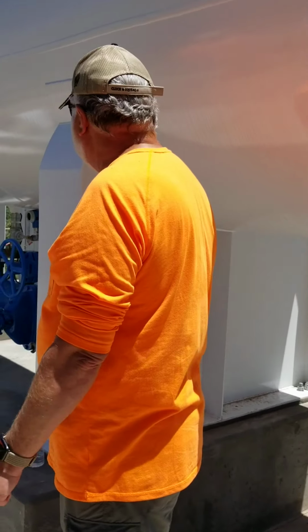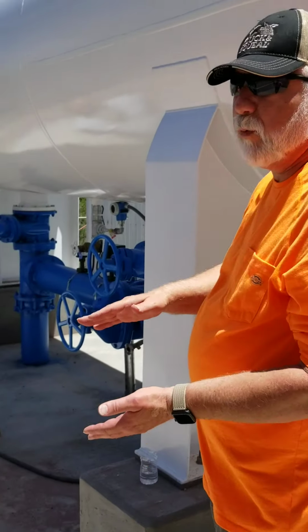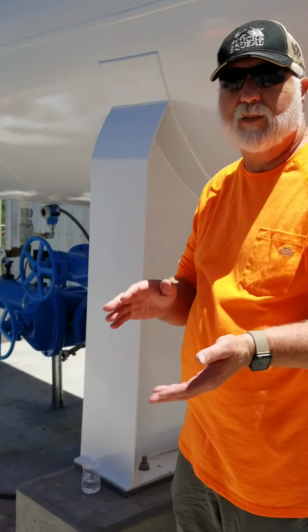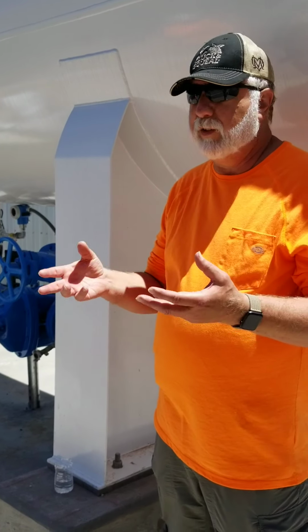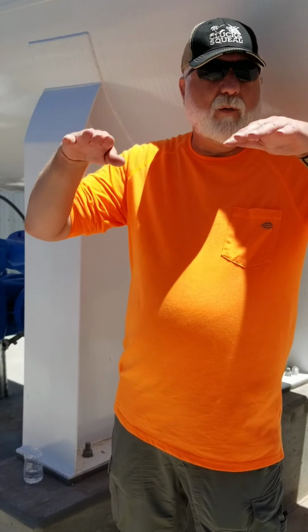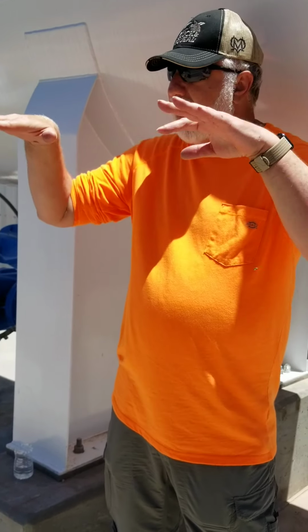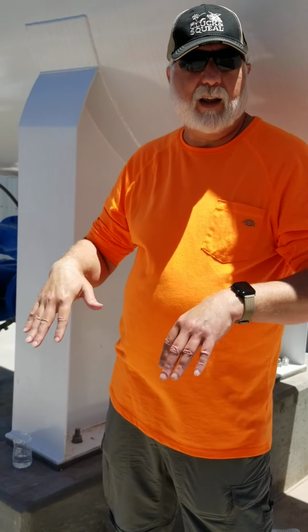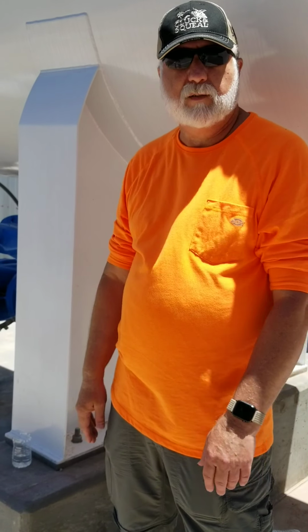And again, as I said, because there is air in contact with water, there's always going to be some loss of air through attrition, which is where the air gets absorbed into the water. So that water level is always going to want to rise up. That's why we have the air compressor, so that if it gets too high, we add air, bring it back down, so we maintain that correct air to water balance for your pumping system.